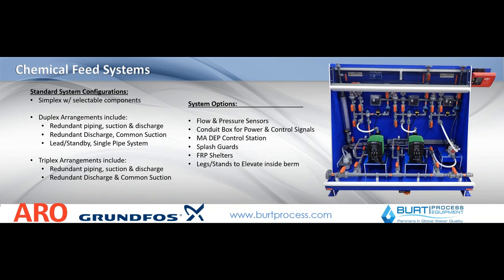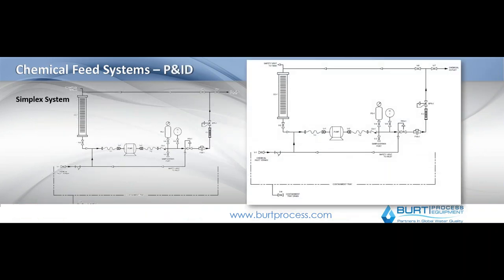Taking a step back from some of the custom, the process equipment standard chemical feed system can take a lot of different directions — whether it goes into environmental closures, containers, PLC, whether it's small at a couple gallons per hour, or large at a couple GPM, VFD-based, different pumps. They all fall within a customizable standard. As a standard, Burt Process Equipment has a few different options: simplex, a couple different duplex arrangements — whether that be duplex redundant or duplex lead-lag with a single piping system — as well as triplex. Looking at a basic simplex design, you have your pump (whether metering, air-operated diaphragm, or gear pump), drawing off of your source, with a wide strainer or chemical strainer, calibration column, flex connectors to prevent pulsation, pulsation dampener, back pressure valve, pressure relief valve, and discharge out.